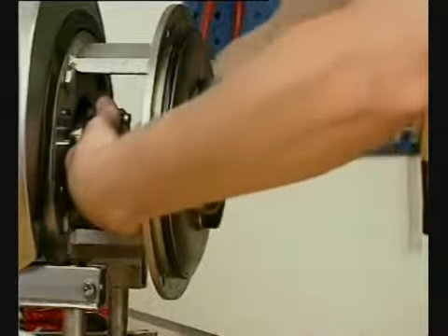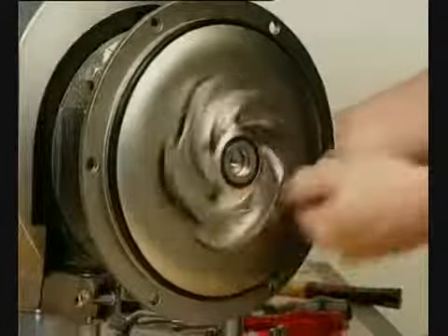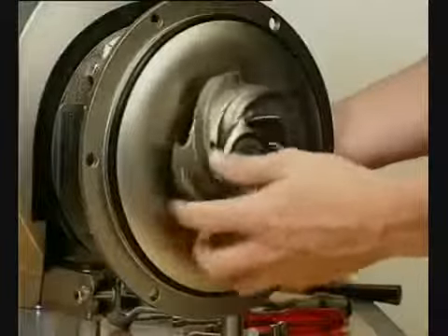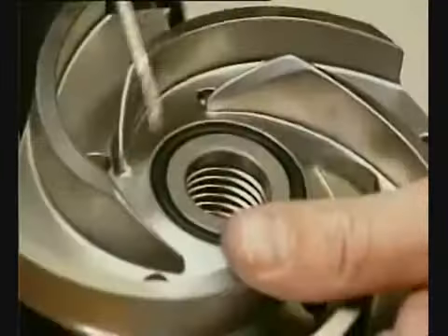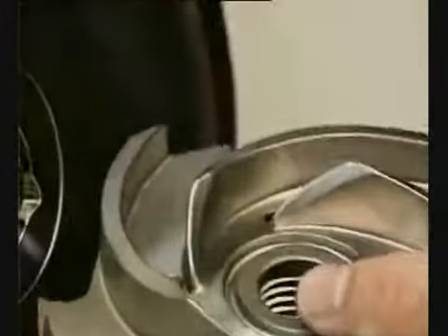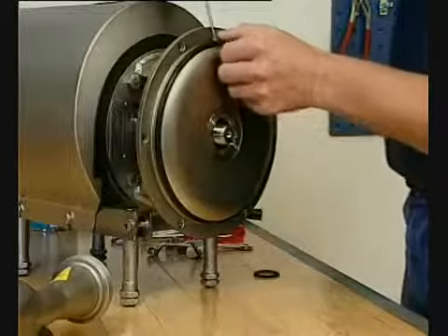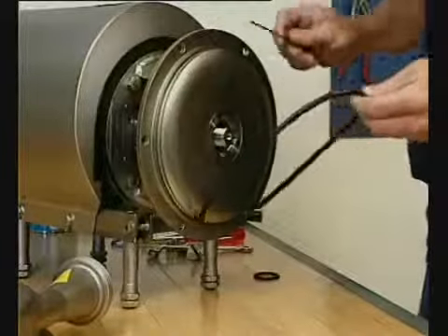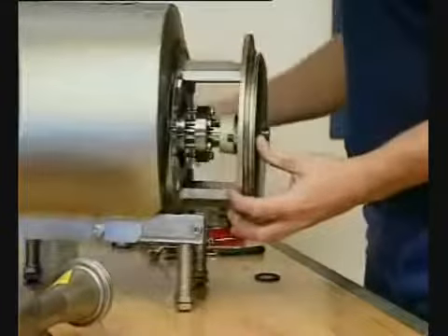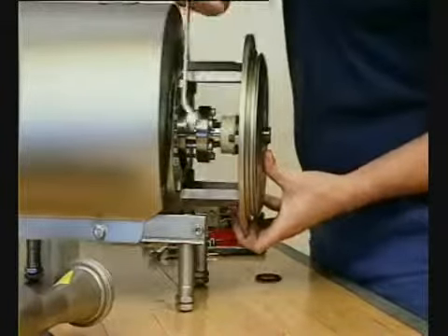If necessary, loosen the impeller by tapping gently on the impeller vanes. Remove the O-ring. Pull off the O-ring. Unscrew the nuts, remove the washers and backplate.